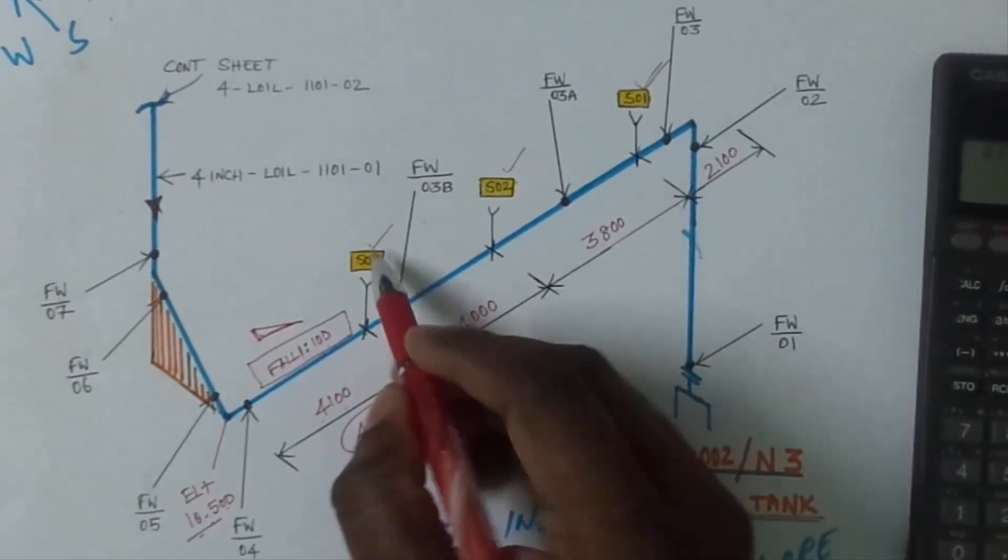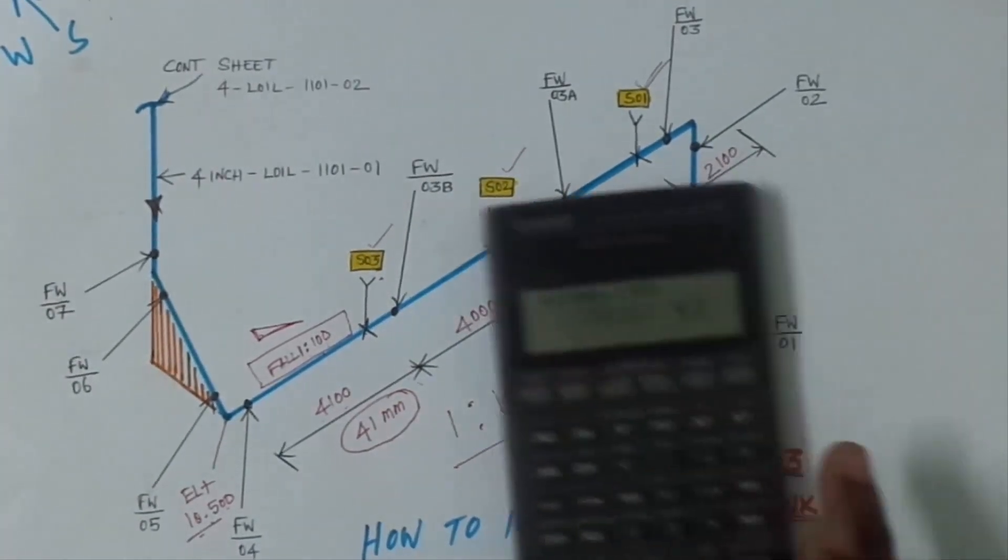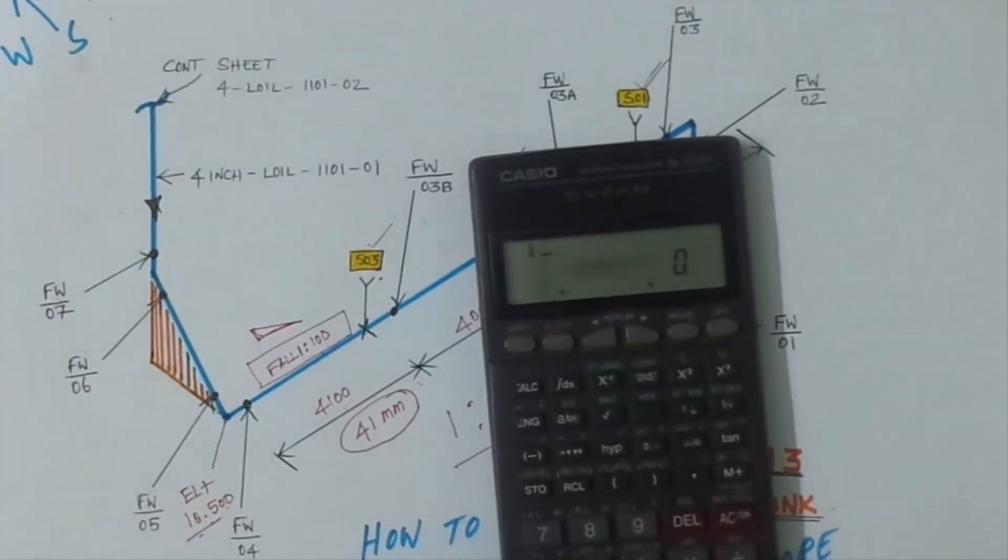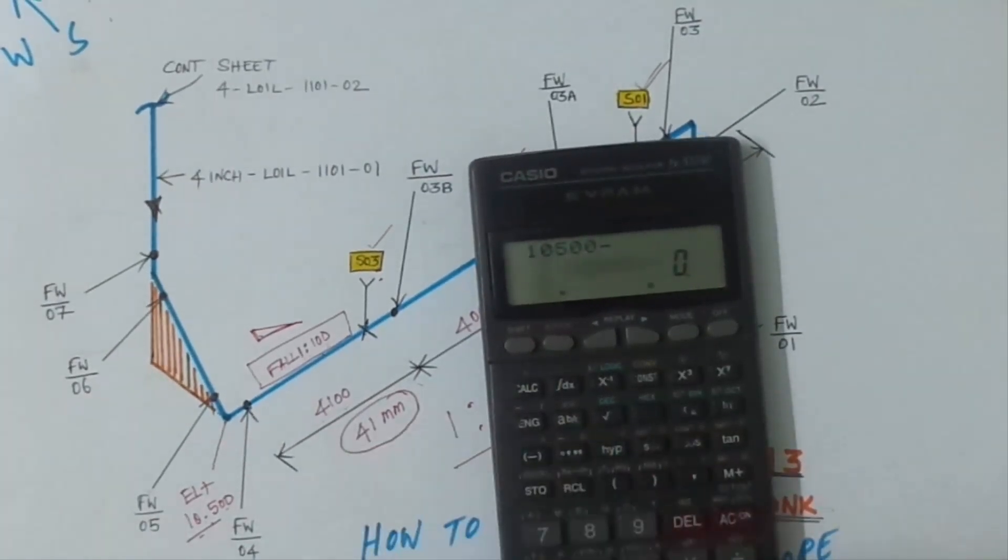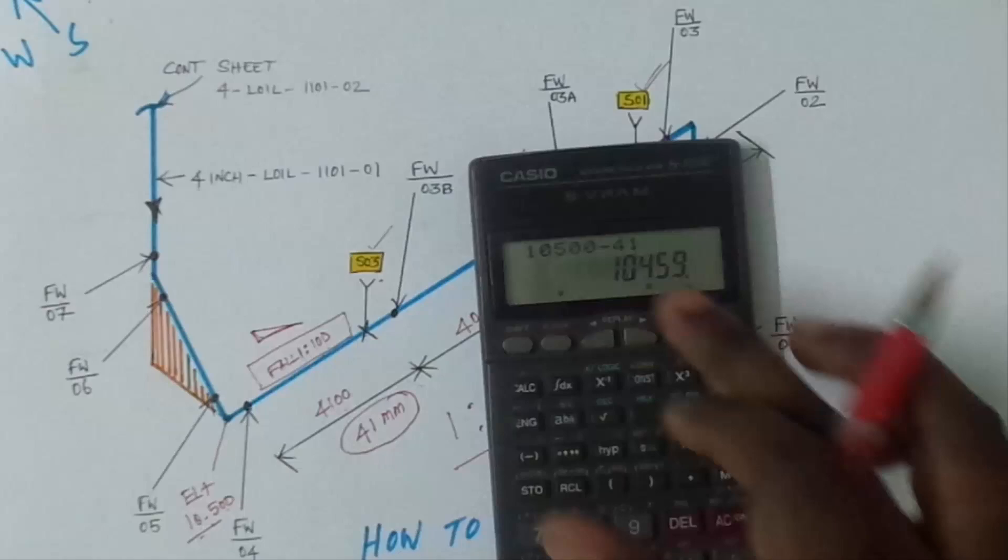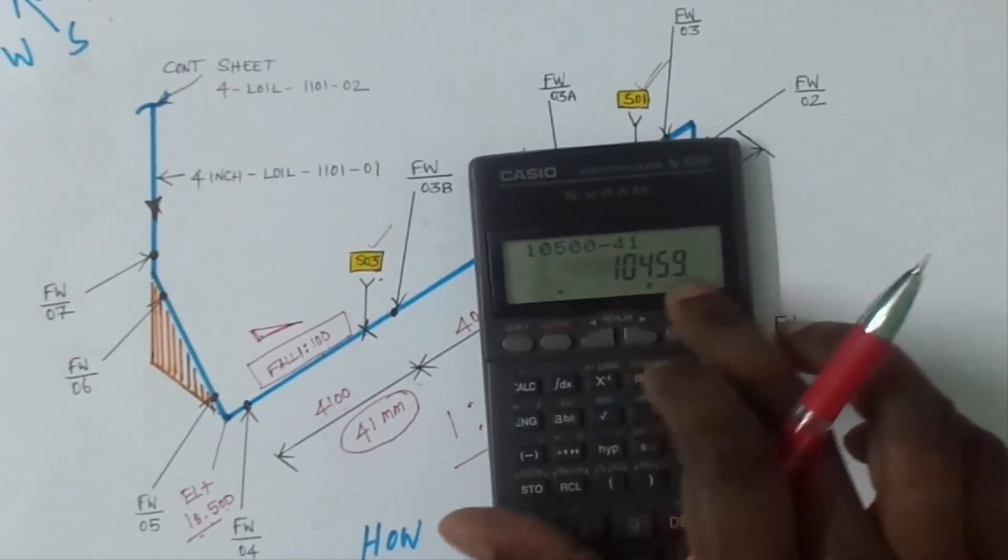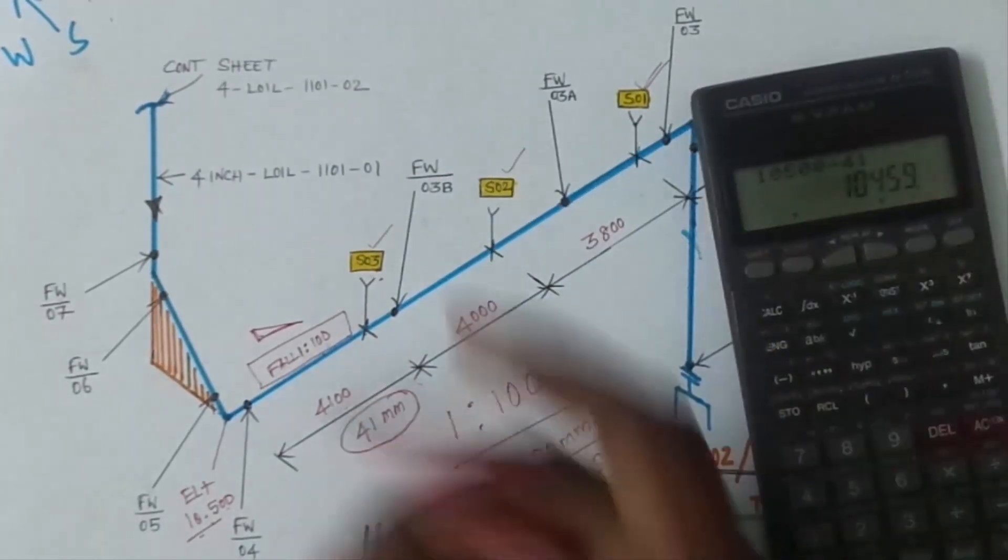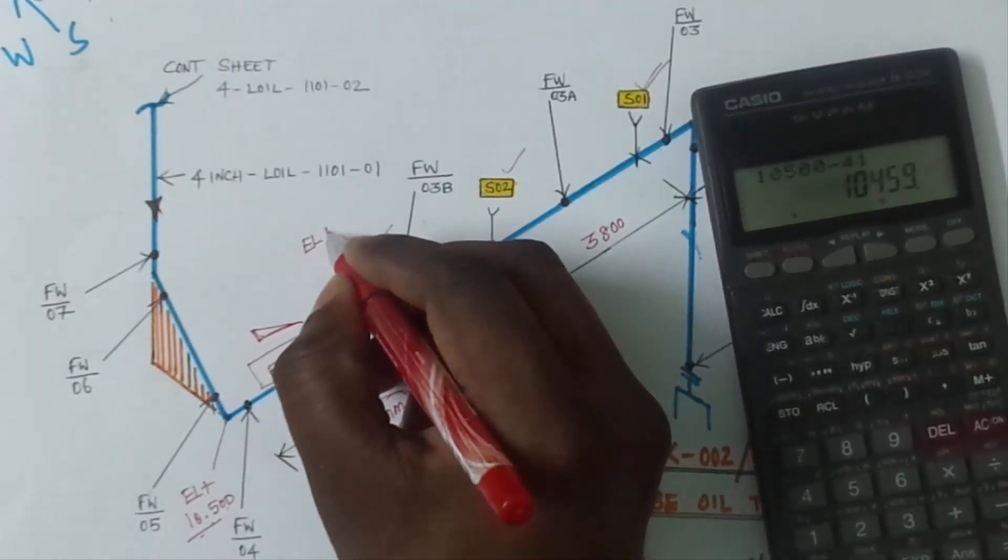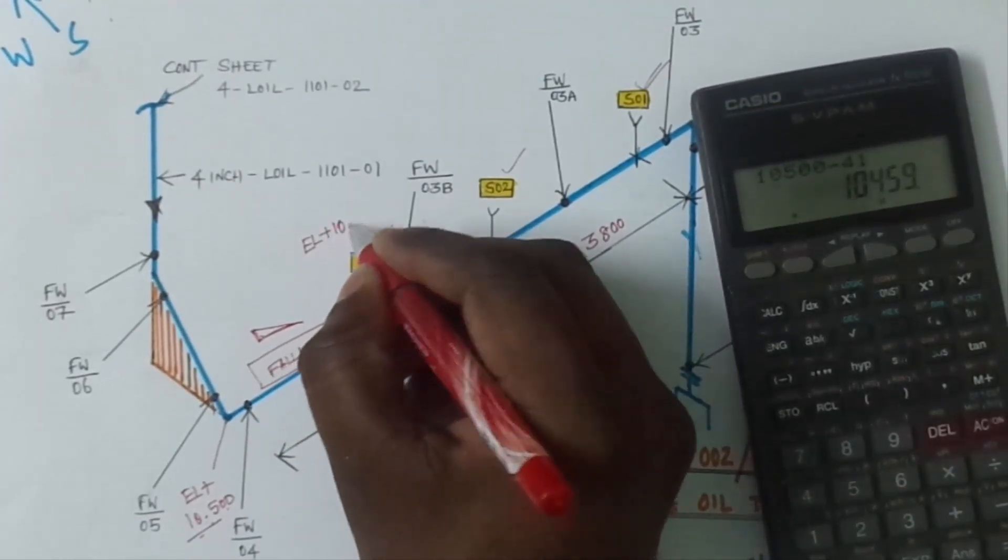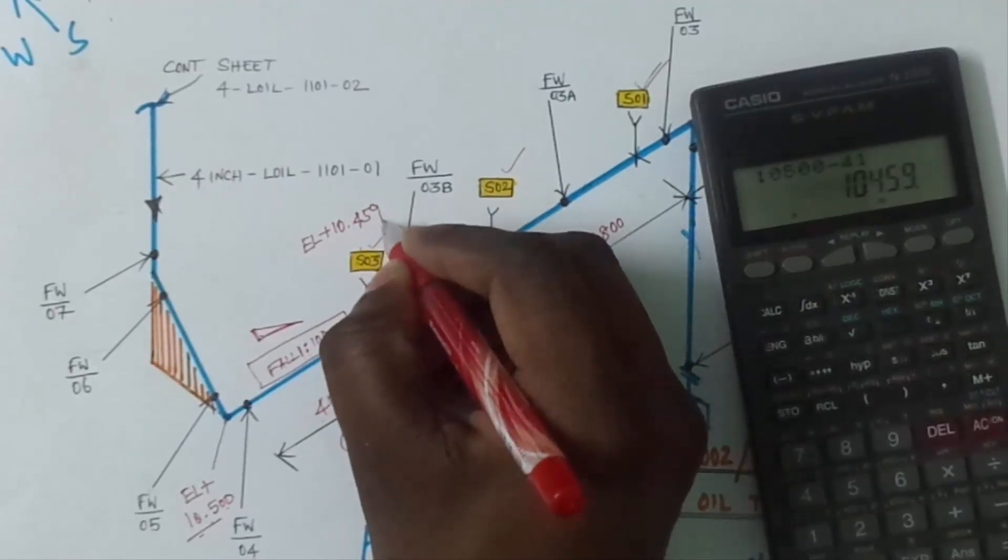So here elevation 10 meter 500. This will go, after that we have to minus 41 mm. So this elevation is 10 meter 459. This support number 3 elevation is 10 meter 459 mm.